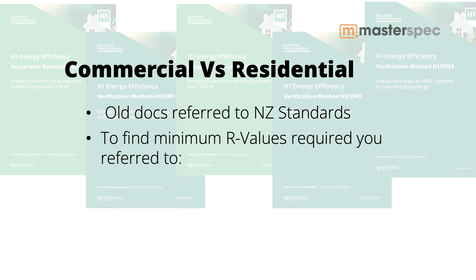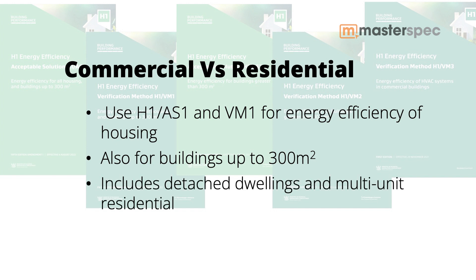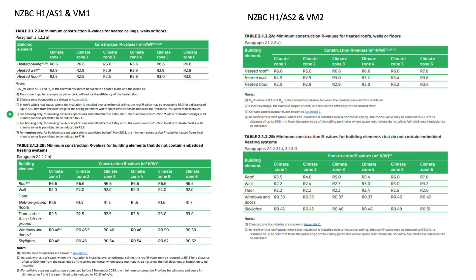As previously mentioned, the existing documents referred to the New Zealand Standards. To find the minimum R values required, you referred to NZS 4218 for housing and NZS 4243 for large buildings. Now we have H1 AS1 and VM1, which apply to the energy efficiency of housing and buildings up to 300 square metres. It's important to note that housing includes detached dwellings as well as multi-unit residential apartments. H1 AS2 and VM2, which are new, apply to the energy efficiency of buildings greater than 300 square metres, excluding housing. So all housing, no matter what the size, falls under AS1 and VM1. Those new documents include tables giving the minimum construction R values required for the various climatic zones.